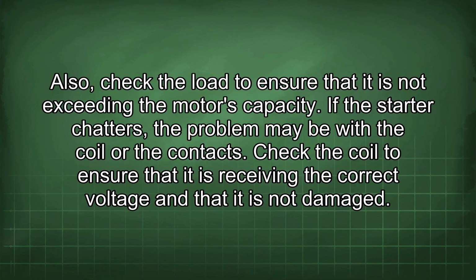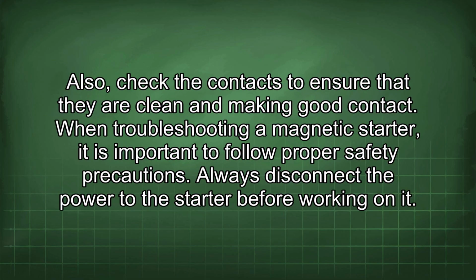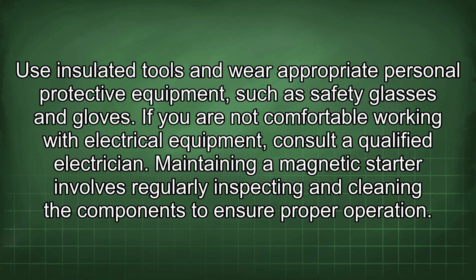Also, check the load to ensure that it is not exceeding the motor's capacity. If the starter chatters, the problem may be with the coil or the contacts. Check the coil to ensure that it is receiving the correct voltage and that it is not damaged. Also, check the contacts to ensure that they are clean and making good contact. When troubleshooting a magnetic starter, it is important to follow proper safety precautions. Always disconnect the power to the starter before working on it. Use insulated tools and wear appropriate personal protective equipment such as safety glasses and gloves. If you are not comfortable working with electrical equipment, consult a qualified electrician.